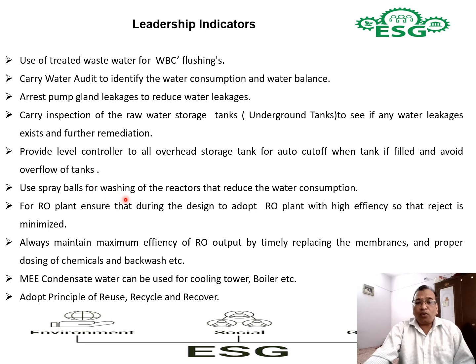Then use spray balls for washing of the reactors, which reduces water consumption. If the reactor volumes are large, like in breweries, big pharma industries, and biotech industries, you find a lot of fermenters of high capacities. I have personally seen how water can be reduced. Initially manual washing was being done. Now spray balls are available. You can see 50% of water consumption has been controlled by use of spray balls. So I insist you use spray balls for cleaning of the reactors.